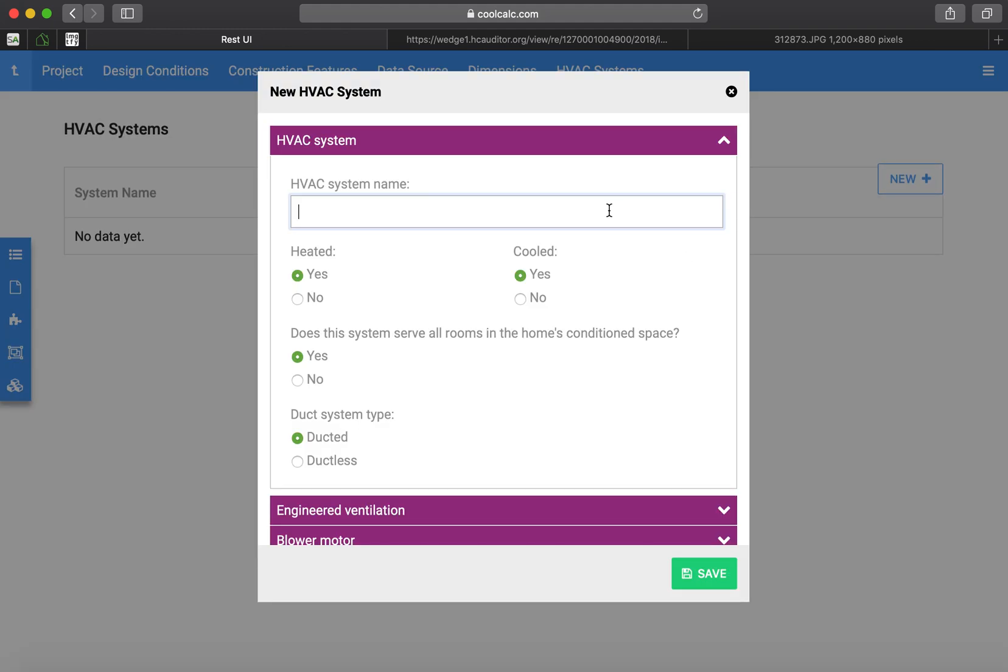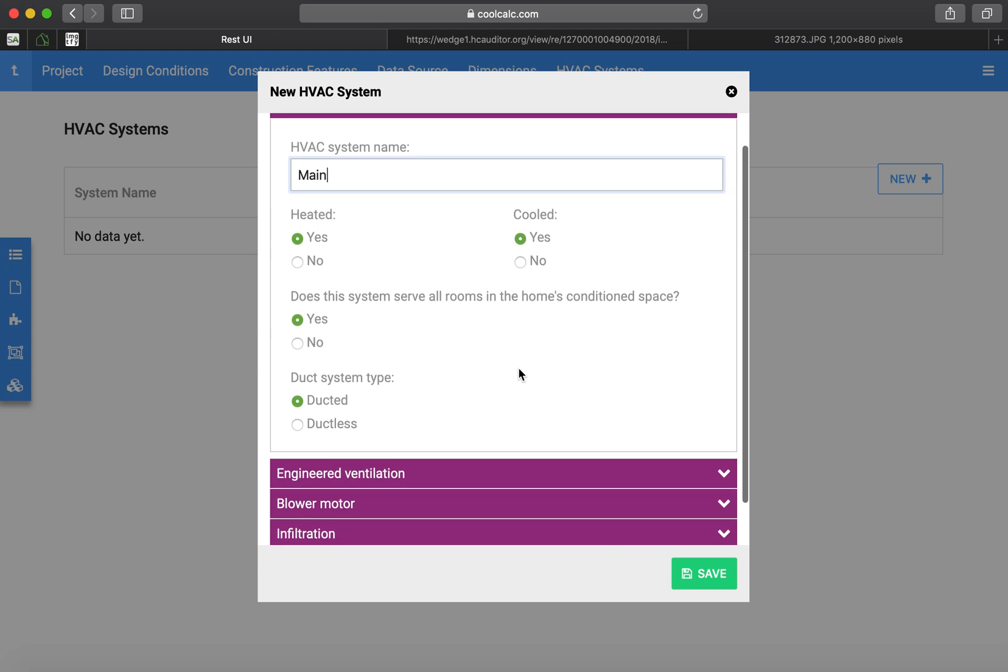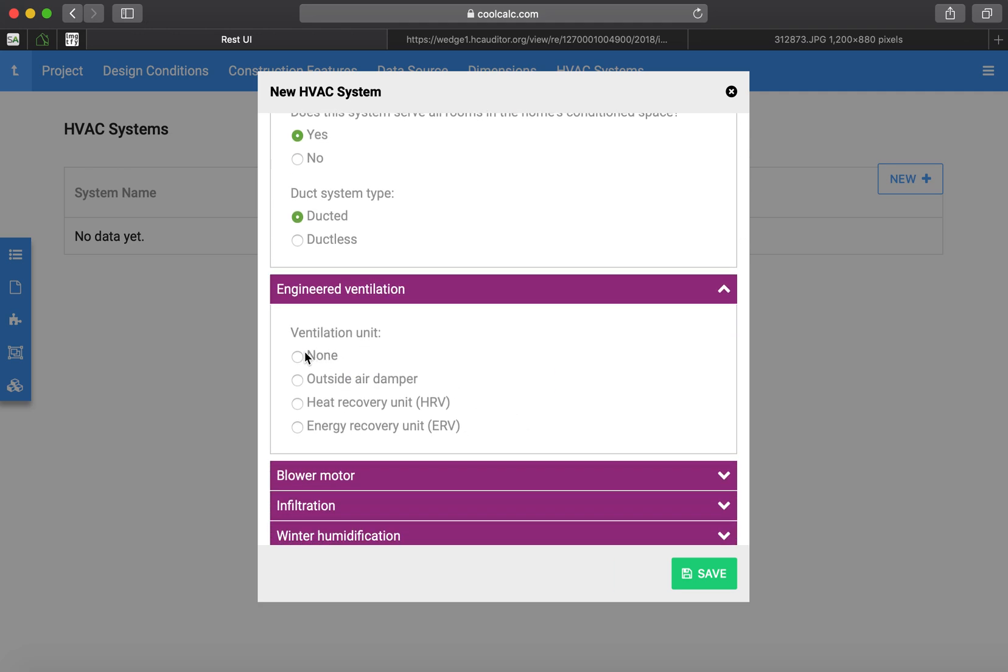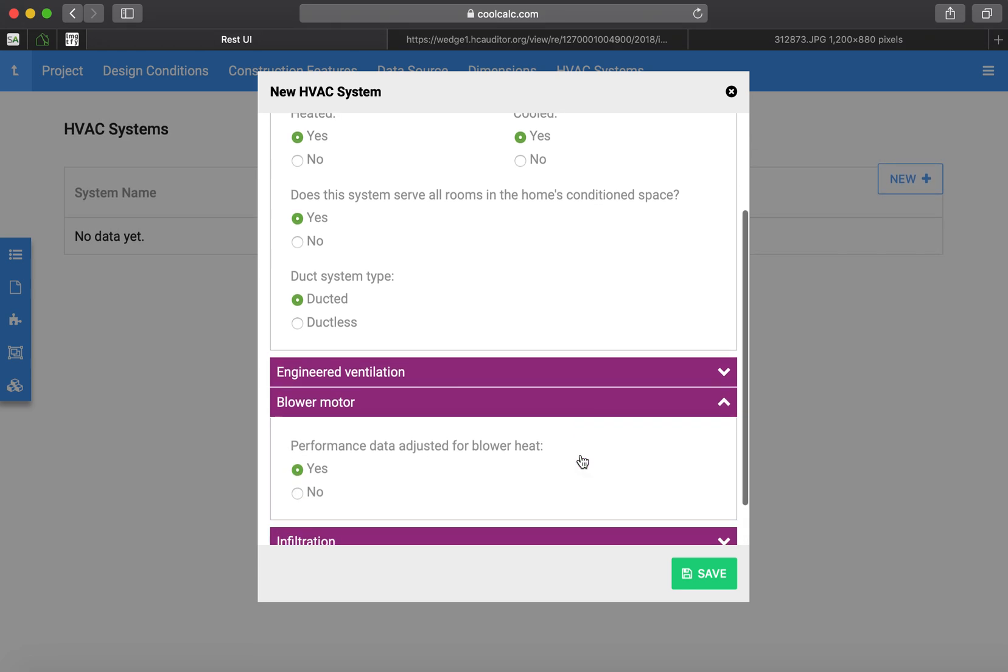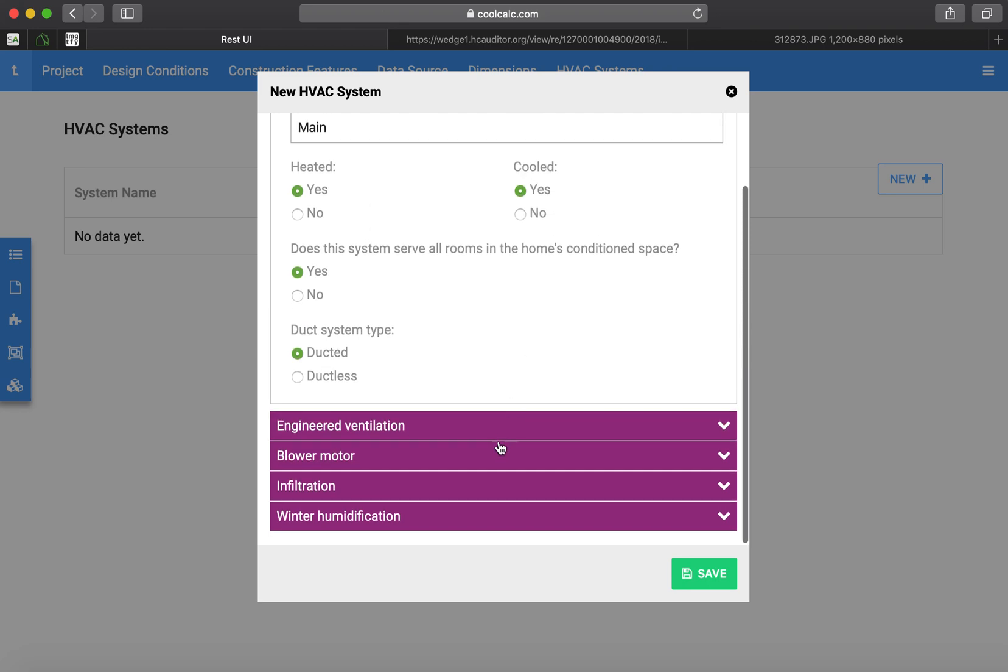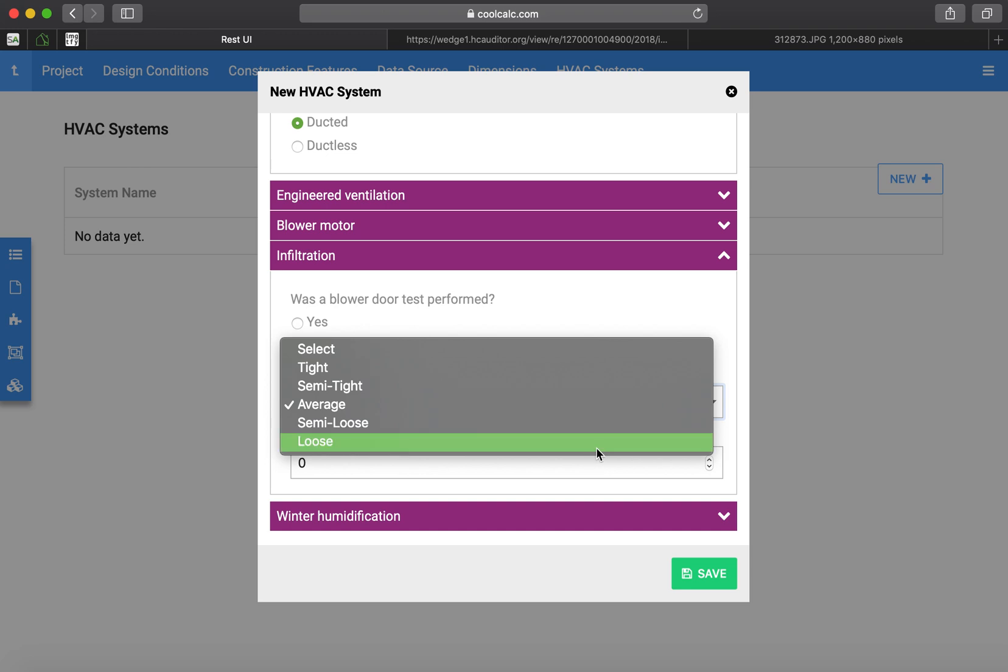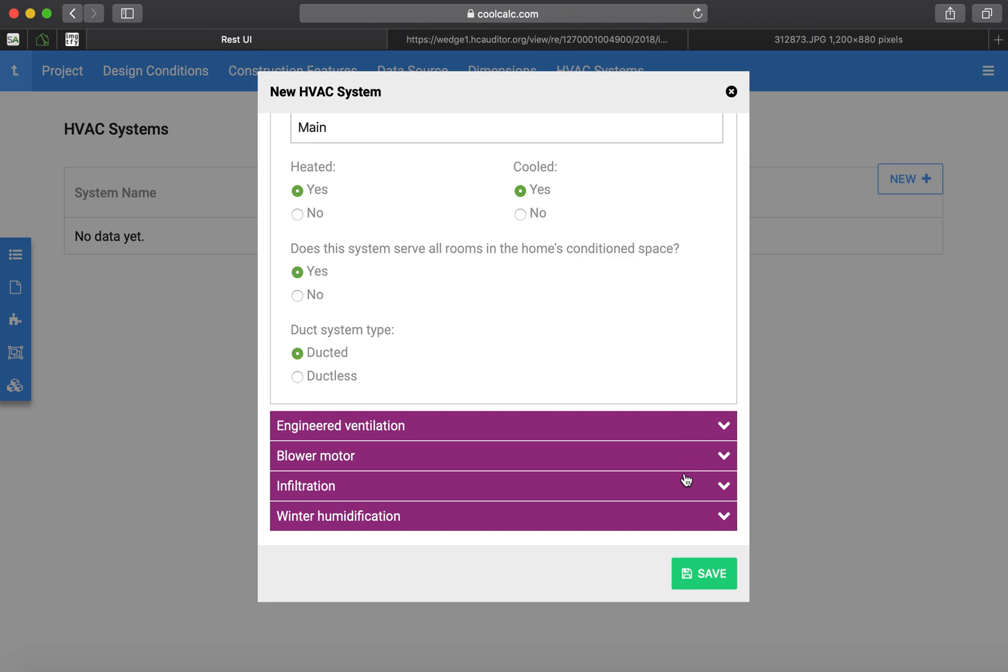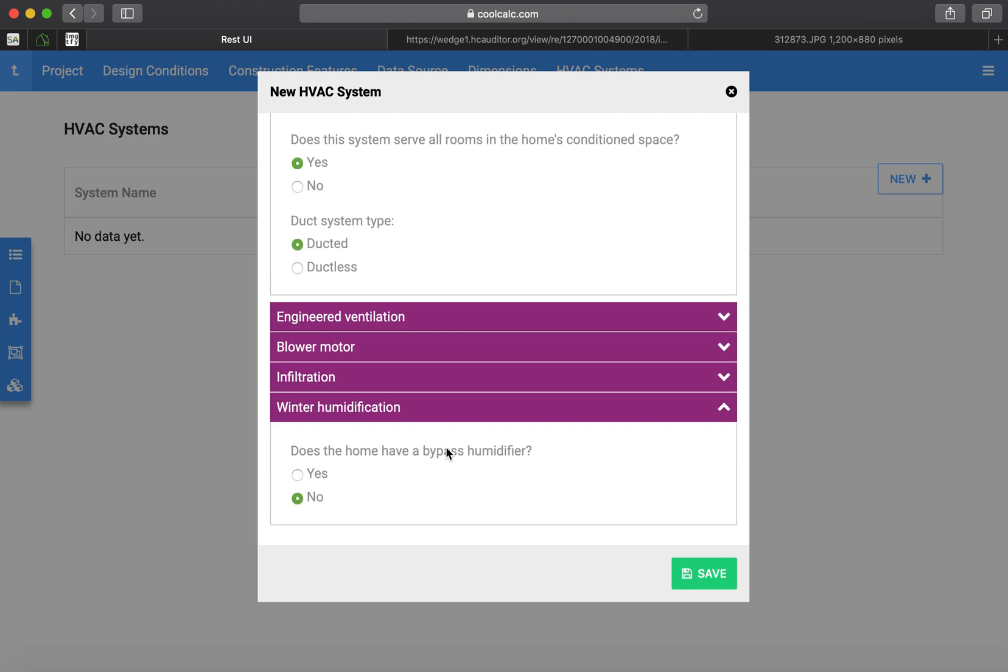Next, we create our HVAC system. I always just call it main, unless there's multiple systems. Most of the homes I deal with don't have that. No engineered ventilation at this time. Blower motor performance is adjusted. This is one I haven't done a blower door test on, and I pretty much always choose loose or semi-loose in those scenarios. No humidification at the time.